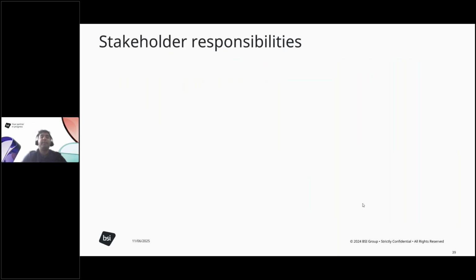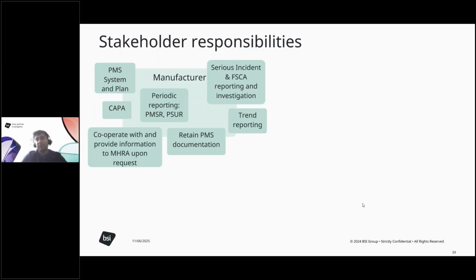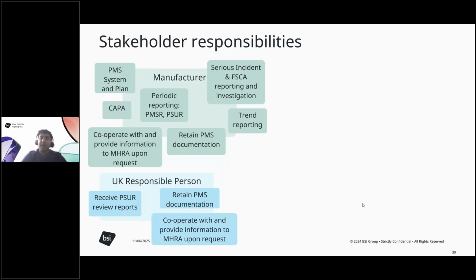So what are the responsibilities for all the stakeholders? If we look at the manufacturer, there's a lot of responsibilities from the manufacturer side. You need to implement the PMS system and plan, look at the periodic safety reporting depending on the classification of your devices, looking at the PMSRs, PSURs, cooperating with and providing information to the MHRA on request, retain the PMS documentation, looking at serious incidents and FSCA reporting, and looking at the trend reporting. From an approved body and UK responsible person perspective, if you are a UK responsible person, you will receive the PSUR review reports, retaining all the PMS documentation, and again, cooperating with and providing information to the MHRA as requested. There are some timelines associated with that in the statutory instrument.